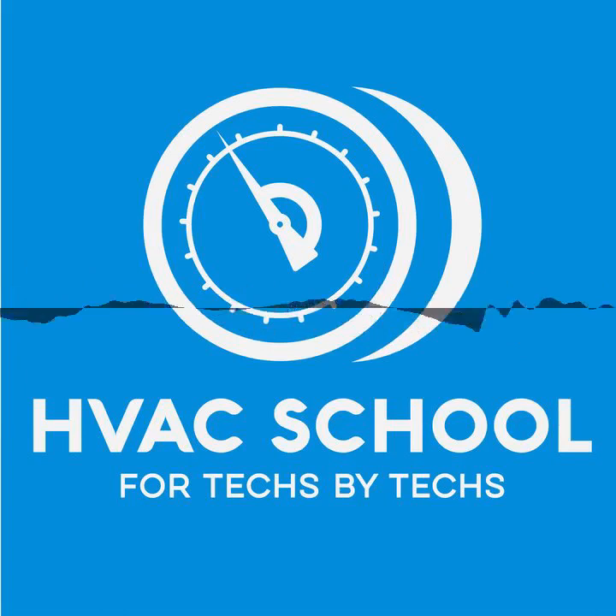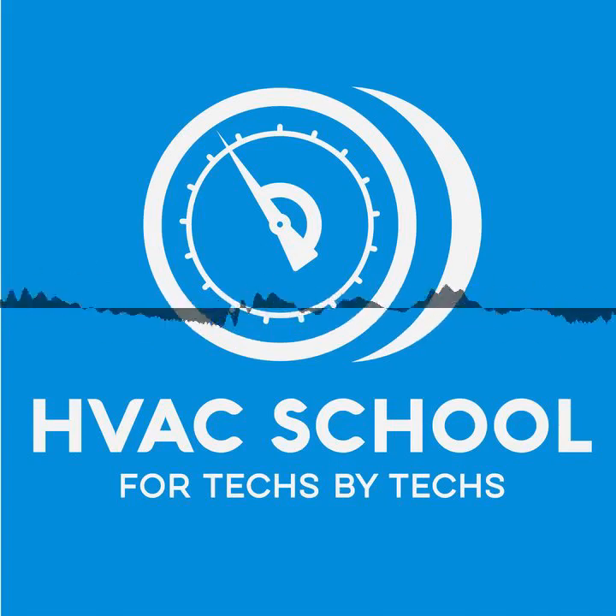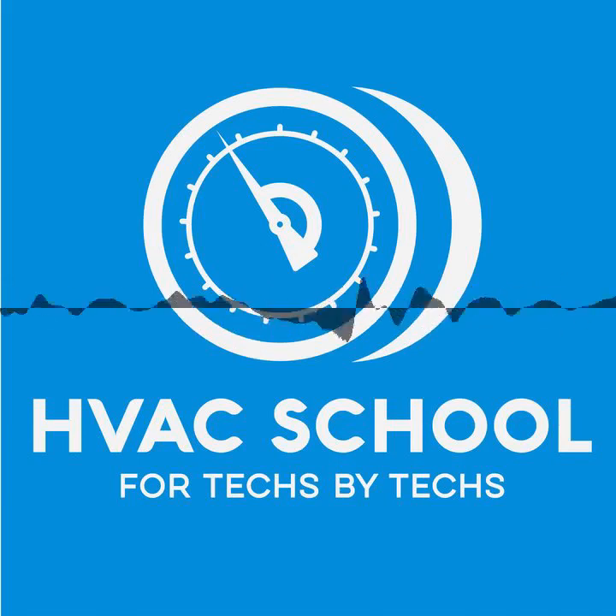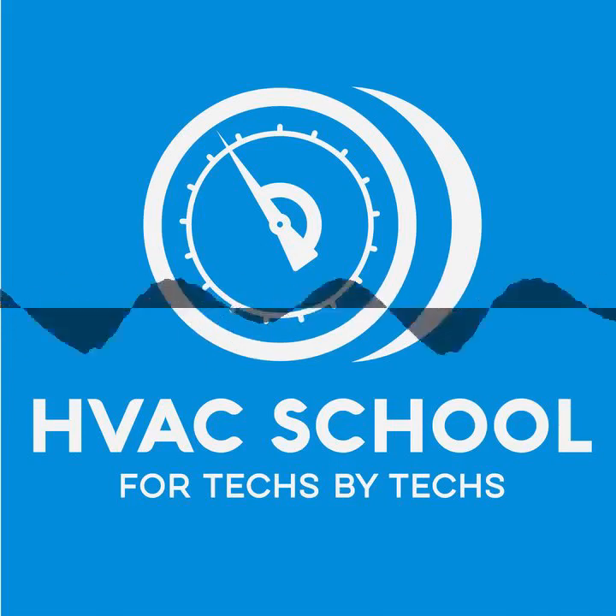Equipment ground shouldn't have any current on it. If it does have a current on it, either it's a very, very small amount, or it's an undesigned circumstance. So let me give you a quick example. Let's say you have a furnace, and there's some current being carried back on the ground wire back to the panel. Well, the only reason that there should be any current on that ground wire would be like with a flame sensing rod, a flame rectifier, where there's a small amount leaking to ground itself for flame rectification. But we're talking a tiny, tiny, tiny amount of current. If any of the current is going out of that blower to ground, that's a problem. It needs to all be carried back on neutral.